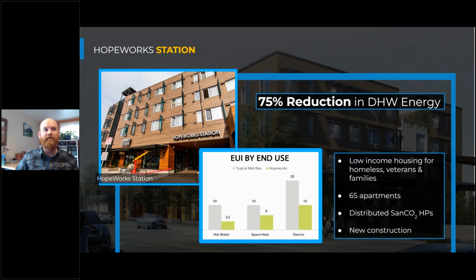So if you're looking at this picture of the building, we're dividing vertically the units. So we have one system that's serving a bank of 3 apartments vertically, and then another system right next to it that's serving another bank of apartments. And this allowed us to use these smaller, more residentially sized products, the CO2 heat pump water heaters, as they have a smaller heat capacity than a lot of our commercial heat pump water heaters, and really result in a low first cost heat pump water heating system. We also were able to reduce the amount of hot water piping by distributing the heat plant systems across the building in a zonal fashion.